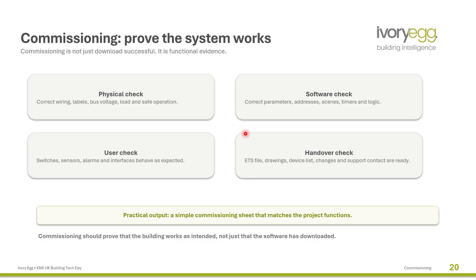Commissioning proves the right design, the right installation, and that the system works. During commissioning you should do a physical check: correct wiring, labels, and bus voltage provided. At least you should have the minimum voltage at the furthest devices you have.